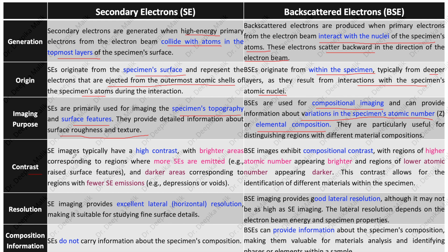Regarding contrast: secondary electron images typically have high contrast, with brighter areas corresponding to regions where more secondary electrons are emitted — such as raised surface features — and darker areas corresponding to regions with fewer secondary electron emissions, such as depressions or voids. Backscattered electron images exhibit compositional contrast, with regions of higher atomic number appearing brighter and lower atomic number appearing darker, allowing identification of different materials within the specimen.